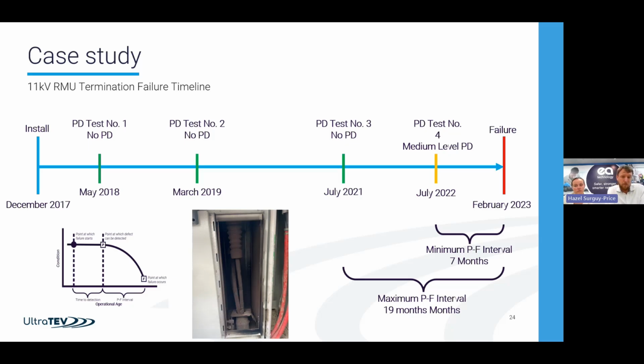So in this particular example, a cable crutch, there are roughly annual measurements going on. I think COVID happened in the middle of that, by the looks of it. And then the first indication of activity is July 2022, when we got a medium level of PD. So it's gone from healthy to medium over that time. The nice bit is that with the latest devices and all the recording, you can actually make quite a good judgment, because even when you got the green, typically you wouldn't have recorded anything, but now you'd see the exact levels. Was there any low level activity going on? It can inform your time to failure. But they had 7 months after this prior to the failure, so a reasonable length of time to react.